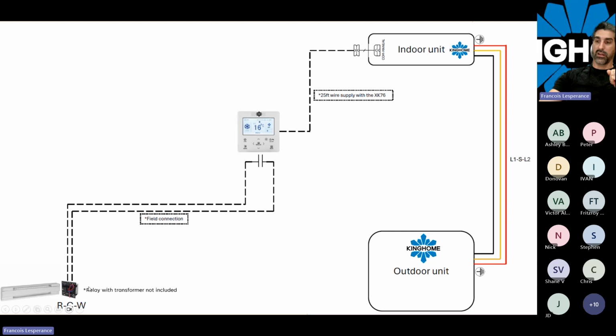Okay, so this is the kind of stuff you guys need to bring on site with you. It's not something that comes inside the box, but the logic here in the thermostat will control this relay. This relay will control a baseboard, for example. And so we now have the ability to interlock the wall unit with the baseboard. Basically, what we want to avoid here is having two different thermostats in the same room, one only for the cooling, for example, and one only to control the baseboard. And so this one can go in cooling mode and the other one can go in heating mode, and you have both units running at the same time. So to avoid that, we have created only one thermostat to be able to control both systems.